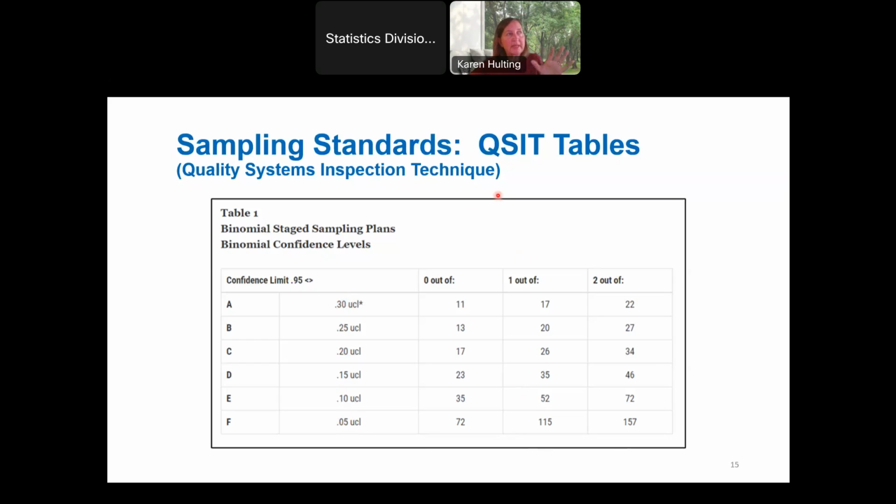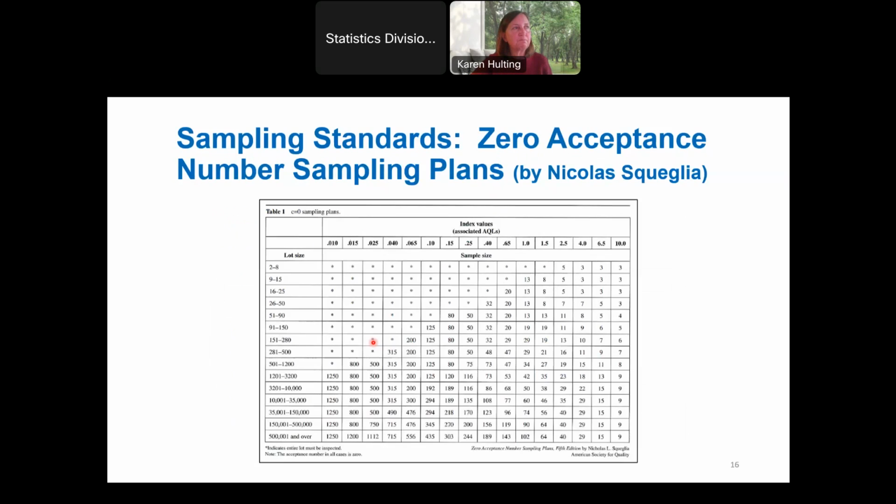It's wonderfully defendable because it comes from Quality Systems Inspection, but if I decide to use the sample size of 35, accept on 0, I still want to run that through an OC curve to really see exactly what the AQL is and exactly what the LTPD is. And you'll find that the LTPD is what is indicated with these numbers in this second column.